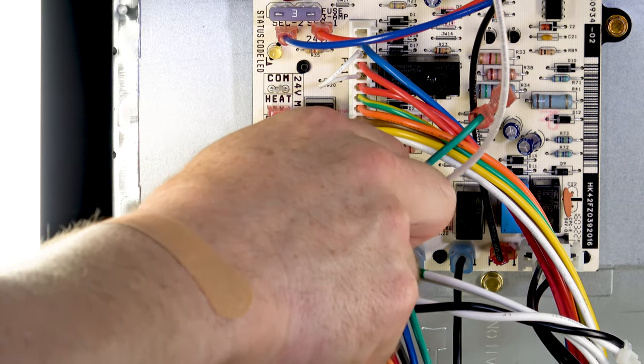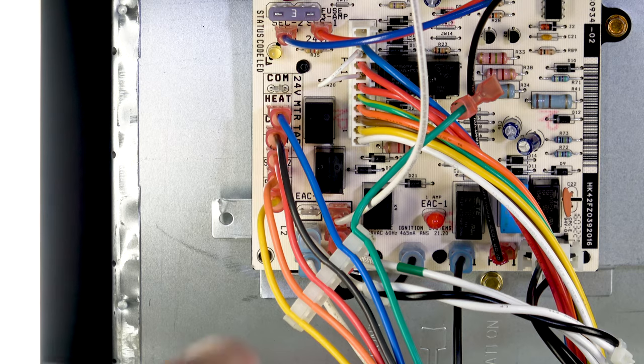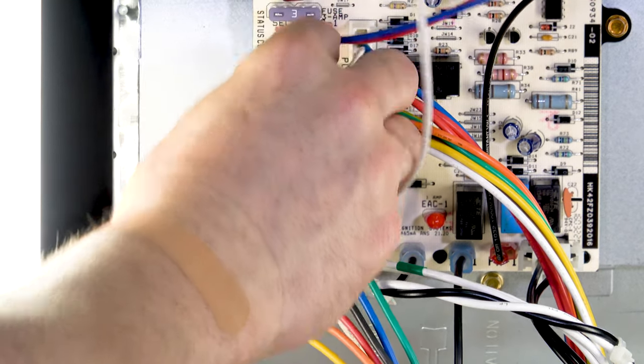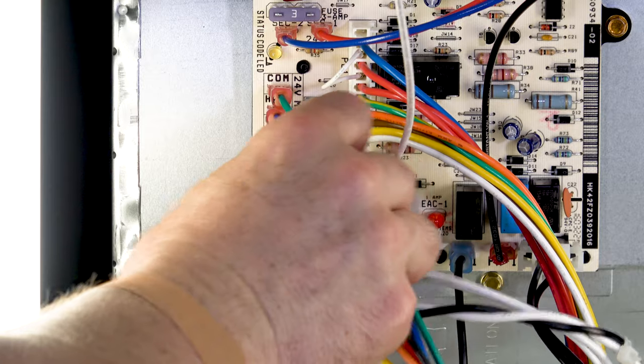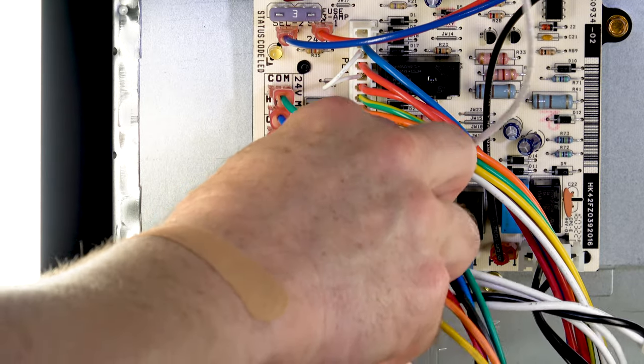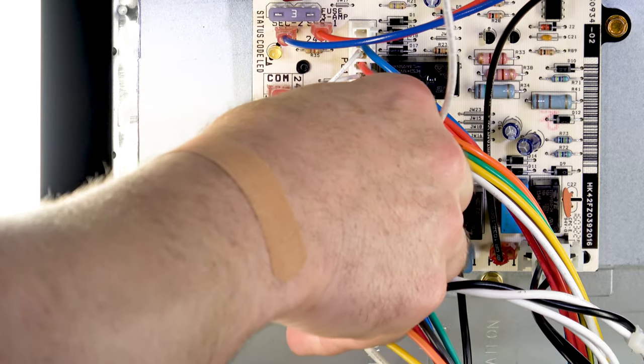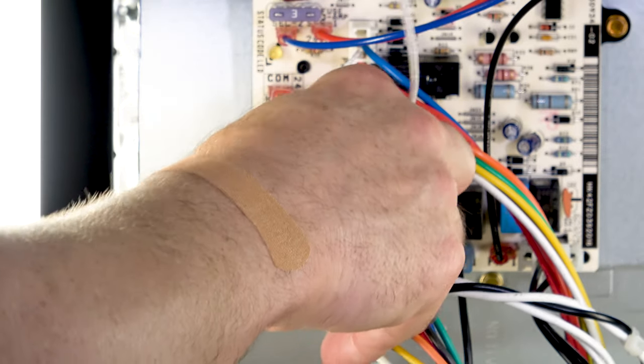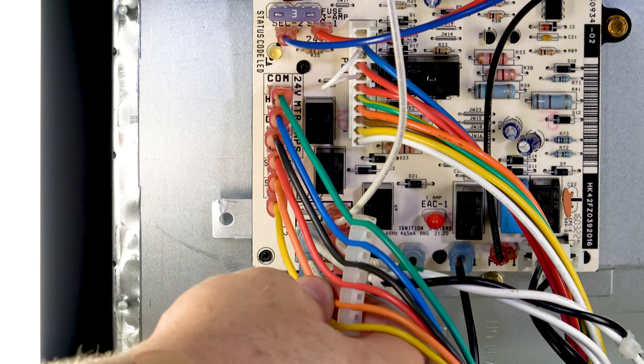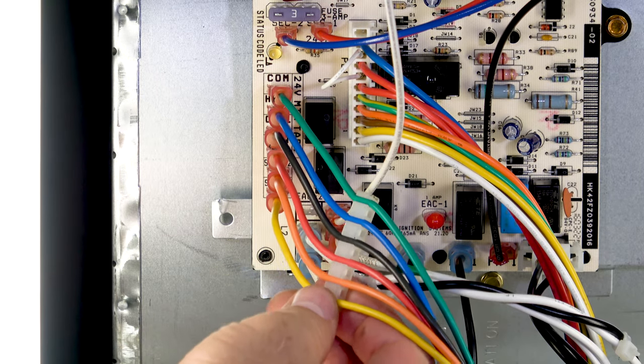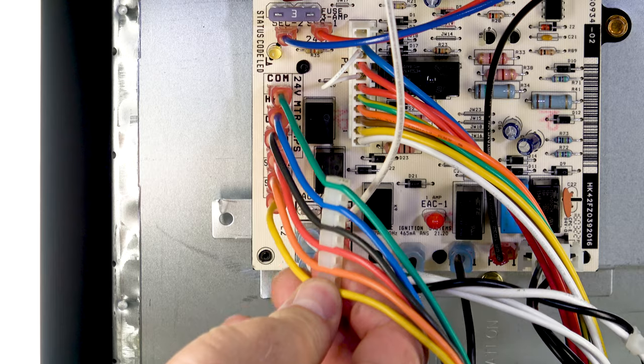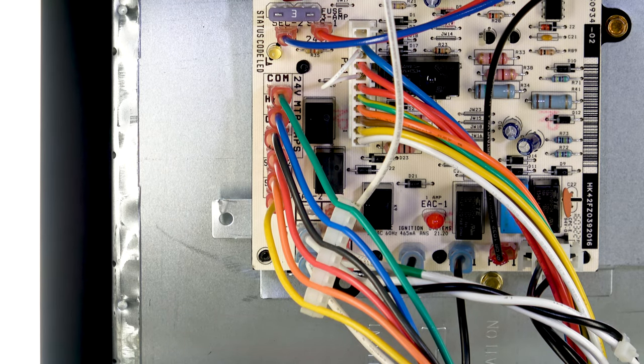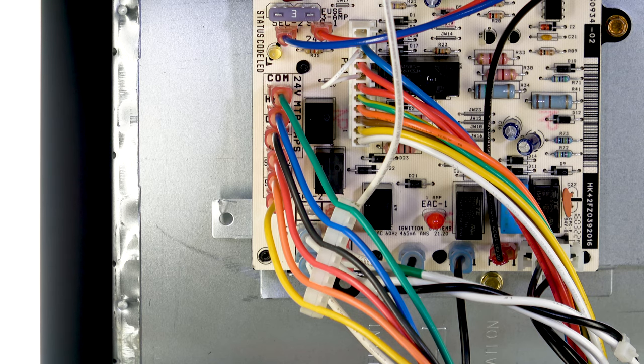The way it's set right now, the speed on your blue wire is set on your heat, your black is going to be your cooling speed, and the red is a circulating speed or fan speed. Those speeds can also be changed. You do have two spare speeds which are on your spare terminals. If you needed to make adjustments as far as airflow in the building or house that you're working with, you would have to reference your product data to see what CFM you may need along with your static pressure in the system.